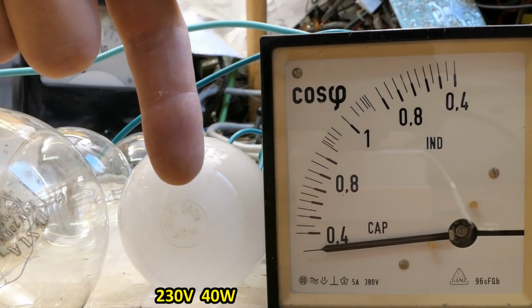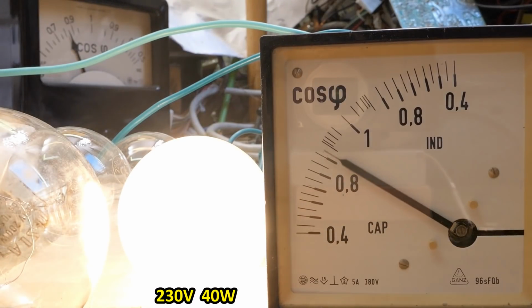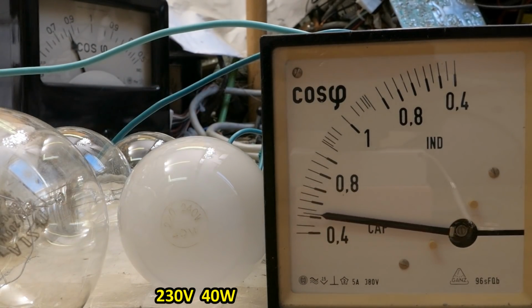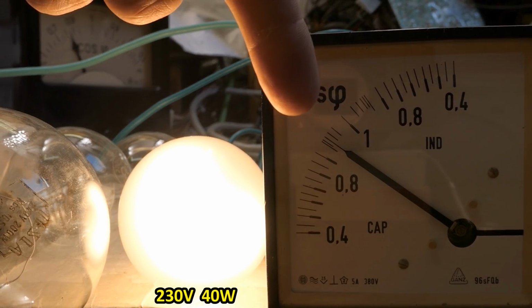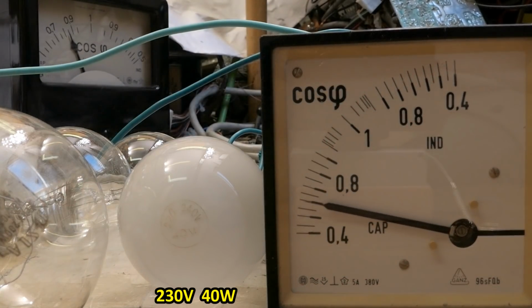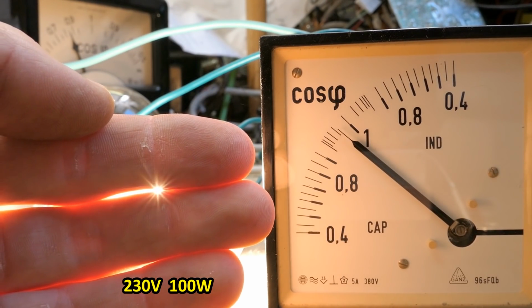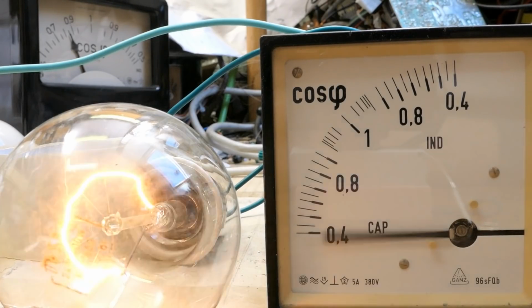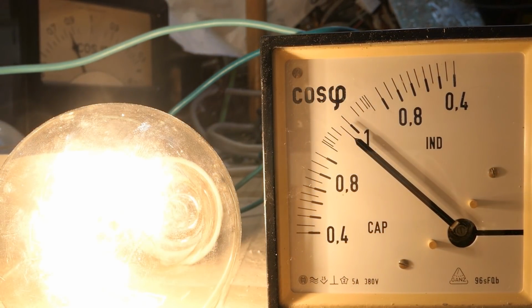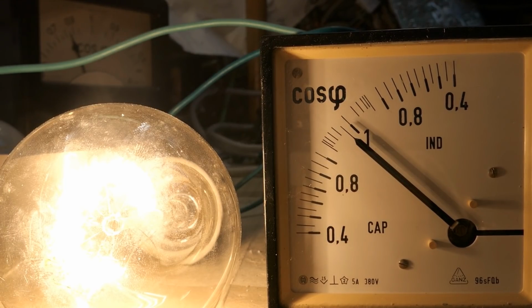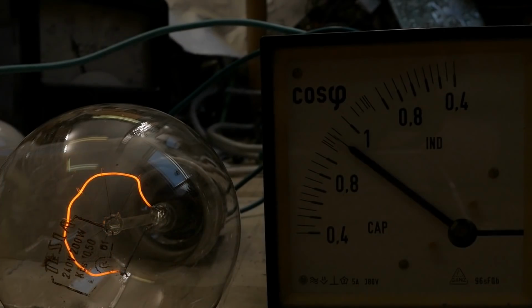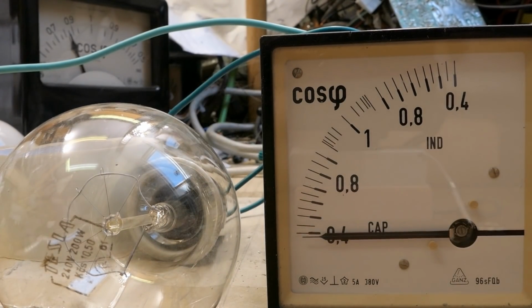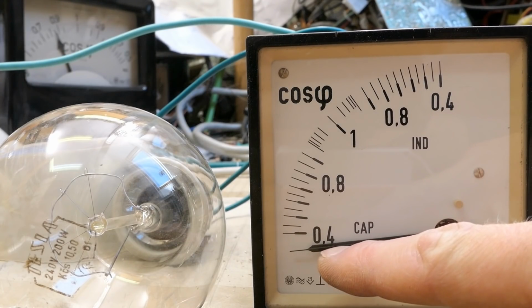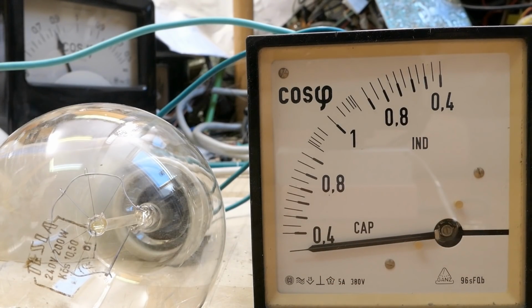Let's try to load it using a 40-watt lamp, which is a purely resistive load, and it does show something. It's getting close to 1, but not exactly there. Now let's try 100 watts, and it's getting closer to 1, and 200 watts, even closer to 1, so it seems to work, but it requires enough load to be accurate. It's more inaccurate when the load is too low.